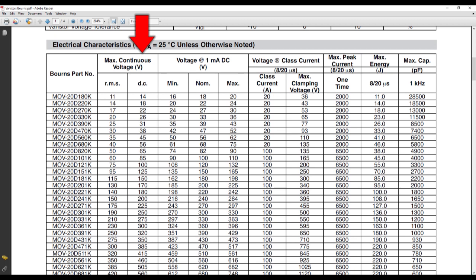The varistor voltage is a classification of the varistor at a current of 1 milliamp. This is the rated single impulse current at a ratio of 8 over 20 microseconds. It is the current that the varistor is able to withstand for a single pulse. This is the class of current and voltage, giving the clamping voltage when the varistor is tripped. And this is the maximum energy, always tested for a ratio of 8 over 20 microseconds. And this is maximum parasitic capacitance, which is relatively high, as you can see.